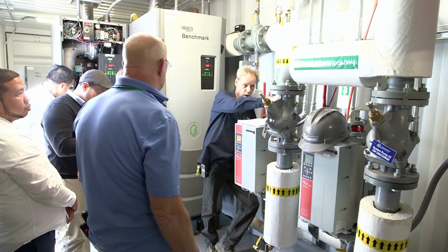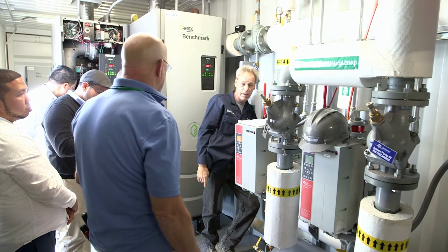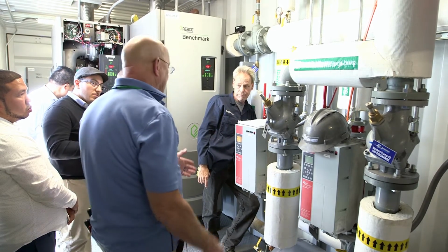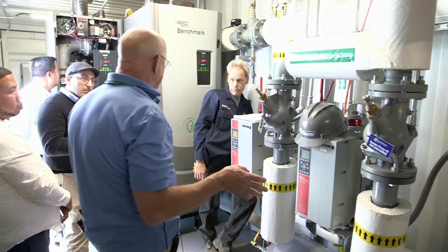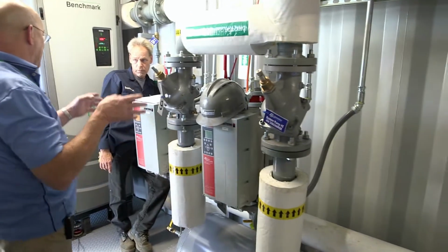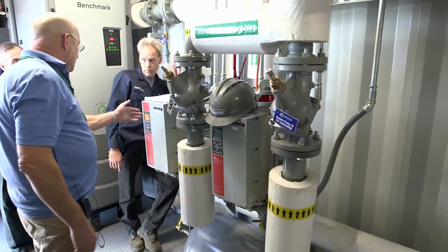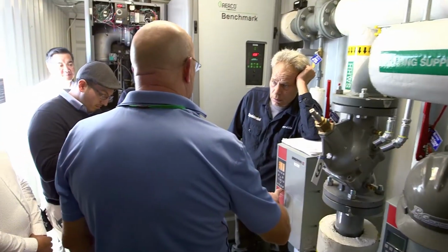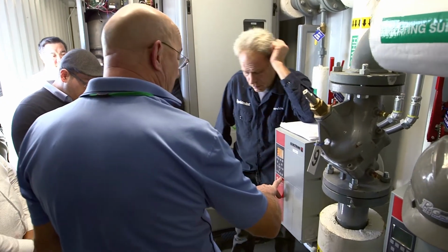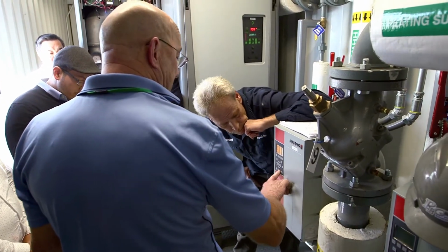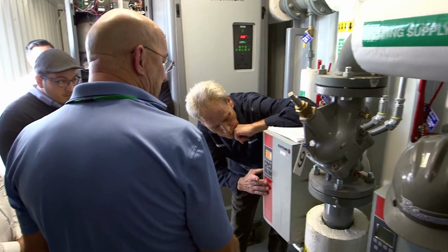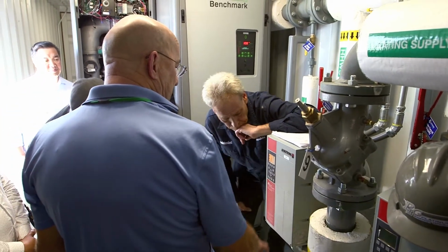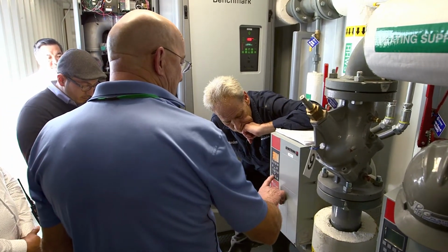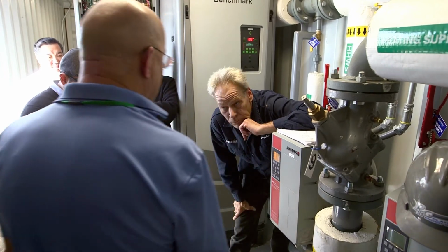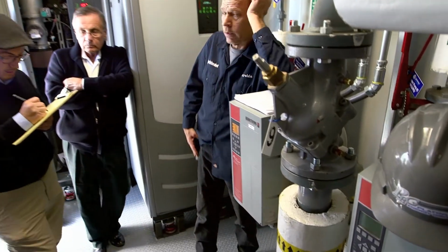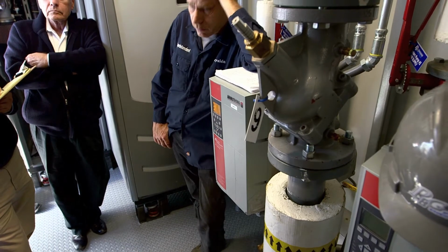Switch it over, turn off, and then switch over. And to do that, you don't even have to turn everything else off. You can leave everything running, just shut these valves, and you can drop that out. It should always be in the auto on. The light for the auto on should be lit. I'll do it for a second here. You see it switches over? That's auto. We'll go back to off because we don't want to have the noise in here right now for you to listen to.